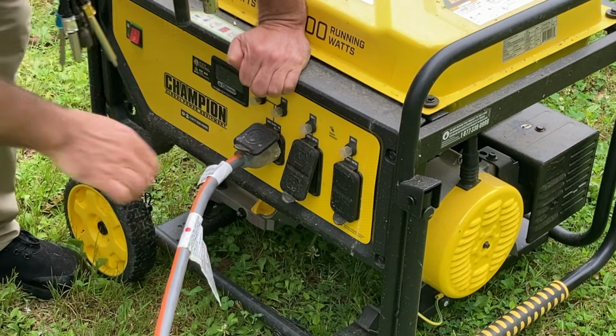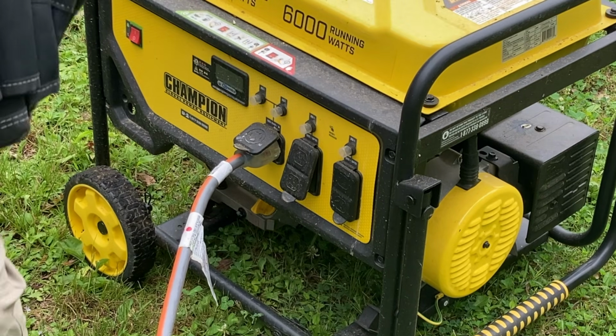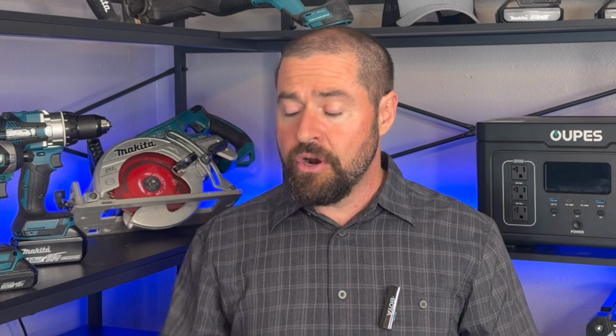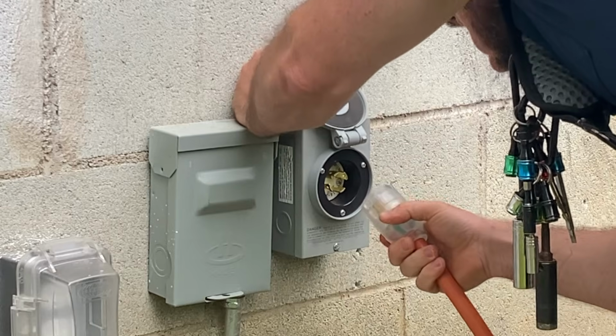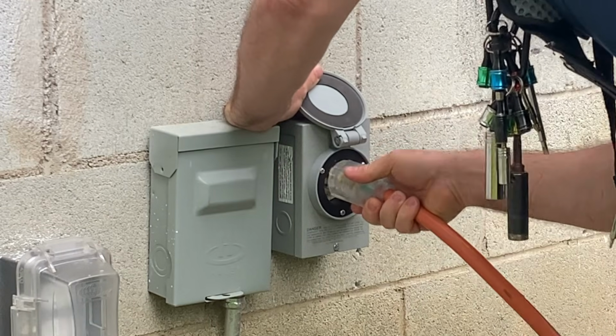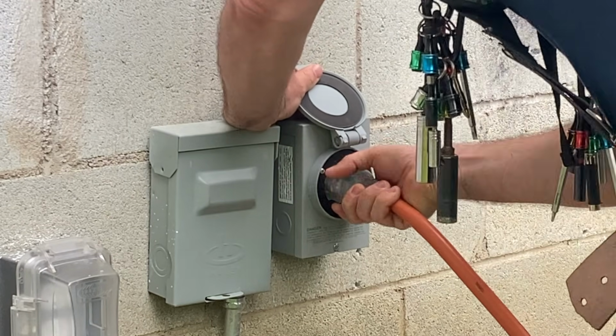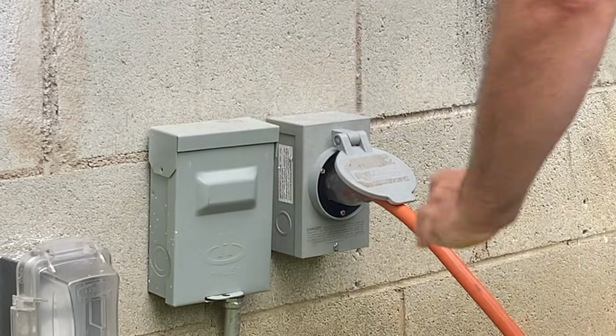The difference is, instead of just running on generator power and burning fuel all day when you don't necessarily need all that power, you can start up your generator, it charges your battery bank back up to full, and then it cuts off. That's going to prolong the amount of runtime you have, save your fuel, and you won't have to deal with the noise - your neighbors won't have to listen to a generator running all day.